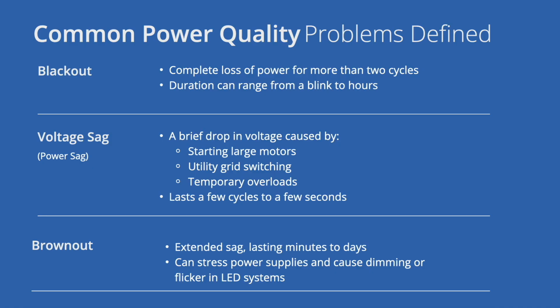Common power quality problems. Define blackout. Complete loss of power for more than 2 cycles. Duration can range from a blink to hours. Voltage sag, power sag. A brief drop in voltage caused by starting large motors, utility grid switching, temporary overloads, lasts a few cycles to a few seconds. Brownout. Extended sag, lasting minutes to days, can stress power supplies and cause dimming or flicker in LED systems.